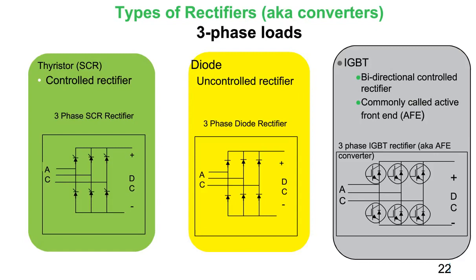Okay, so jumping right into it, the first solid-state rectifier device deployed, which is still in use today, is the thyristor, also known as the SCR. This device is used to provide a precisely controlled power flow into the DC bus from the product. The 3-phase thyristor typically has a lagging power factor when not operating at full load amperage. The DPF tends to get worse as the load decreases. Also, harmonics are caused in the rectifying process. Harmonic current amplitudes are typically worse at full loads. And the third effect is that in the process of turning off a conducting device, a momentary short circuit occurs on the AC lines. This causes voltage notch, as seen above.